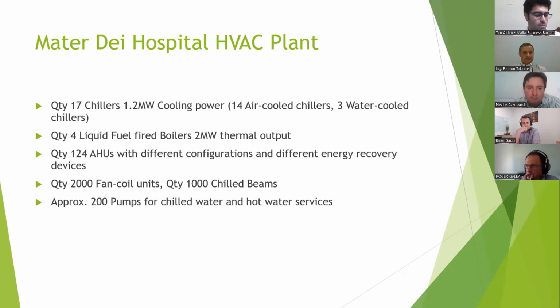So this is the plant that we have. We have 17 chillers of 1.2 megawatt cooling power each. We have 14 air-cooled chillers and 3 water-cooled chillers, 4 liquid fuel-fired boilers of 2 megawatts thermal output, and 124 AHUs, air handling units, which handle the ventilation, cooling and heating, and the humidification of the fresh air going into the hospital.